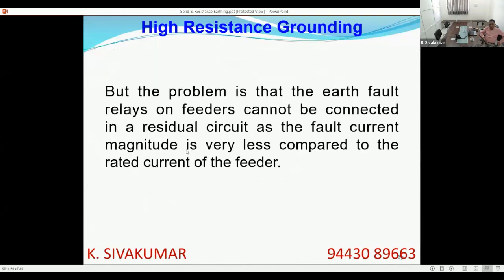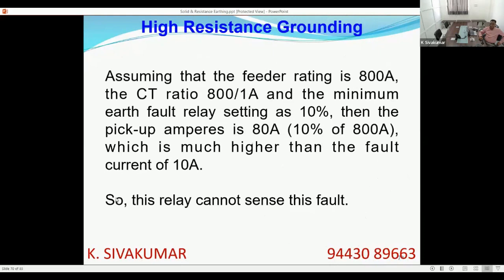But the problem is you cannot achieve current based protection. Conventional earth fault relays cannot be connected in a residual circuit, as the fault current magnitude is very small compared to the rated current of the feeder. We will take an example. I have a feeder of 800 ampere, CT ratio 800 by 1 ampere. The earth fault relay setting is 10% of 800 ampere, that is 80 ampere. Suppose I provide this relay in this system, it will never trip because the current is only 10 ampere. There is no point in providing a relay in the first place.